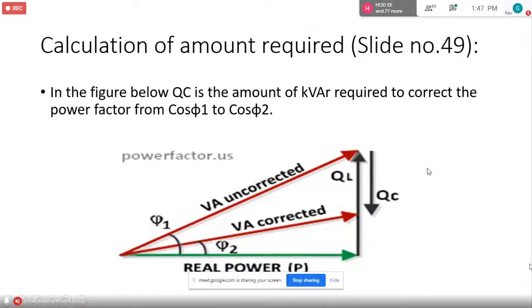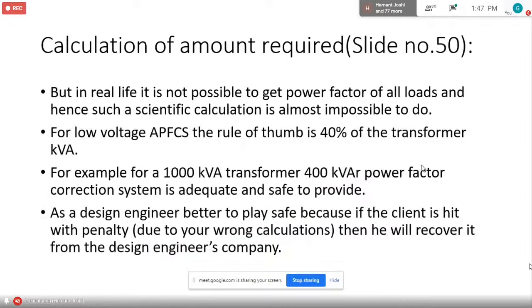In practice, you cannot use this method. I'll tell you why. In real life, it is not possible to get the power factor of all loads, and hence such a scientific calculation is almost impossible to do. For low voltage APFC, the rule of thumb is 40% of the transformer kVA. So if your transformer is 1000 kVA, then a 400 kVAr capacity power factor correction system is adequate and safe to provide. Scientifically, you would have to get each and every type of load and its power factor, kW and kVA, but this information is not available in practice, so you cannot do it.